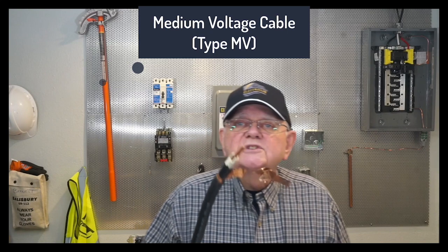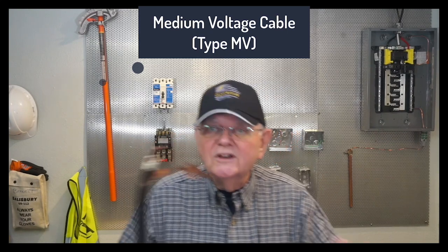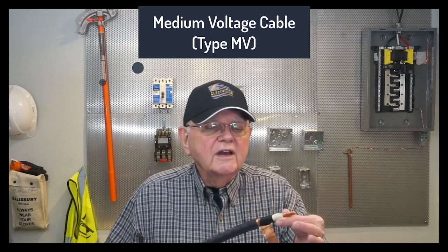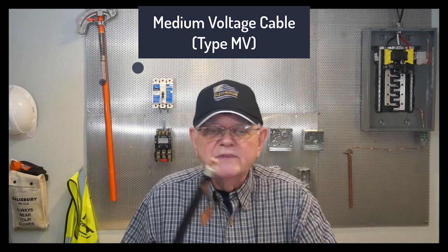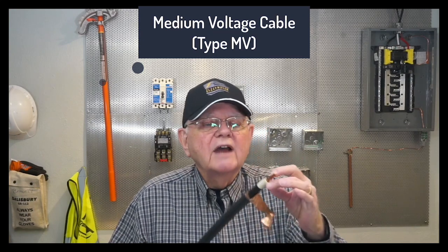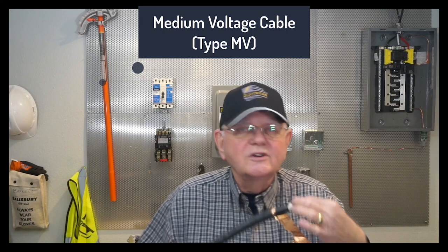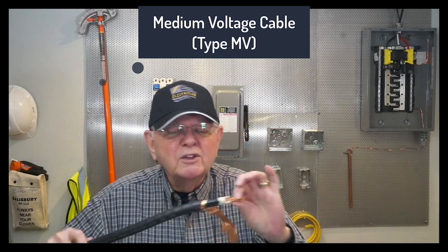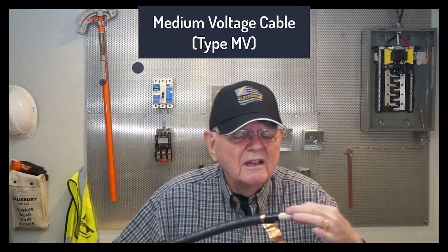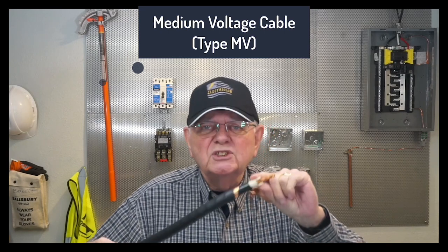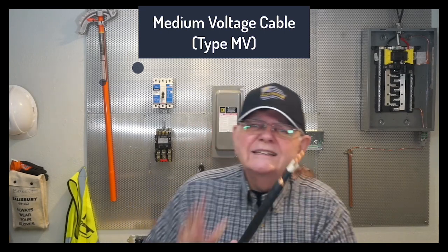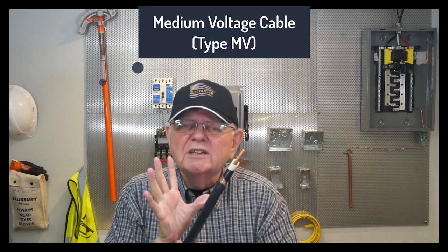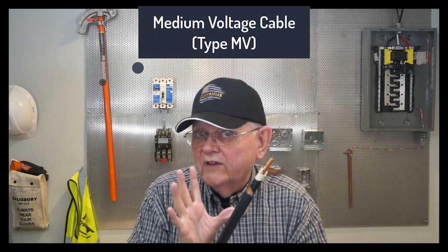And medium voltage cable is obviously constructed differently than normal cable. Here I've got a single conductor. This happens to be a copper conductor. I've got an extruded semiconductor. It's a black layer. You can barely see it underneath the white insulation that you see. The whole idea with medium voltage cable is I create a lot of voltage stress.